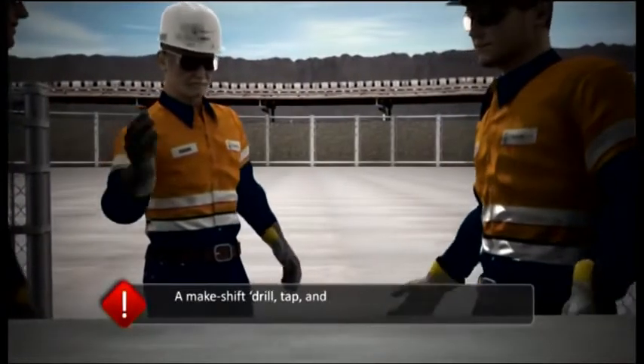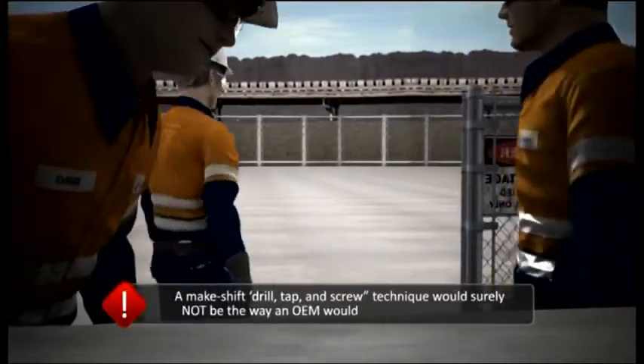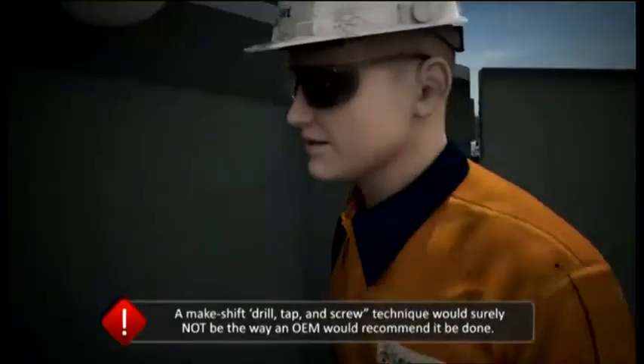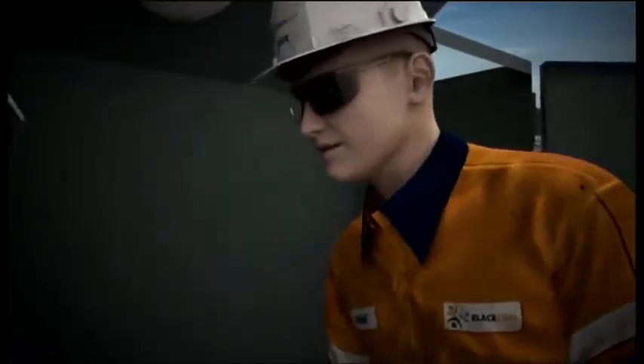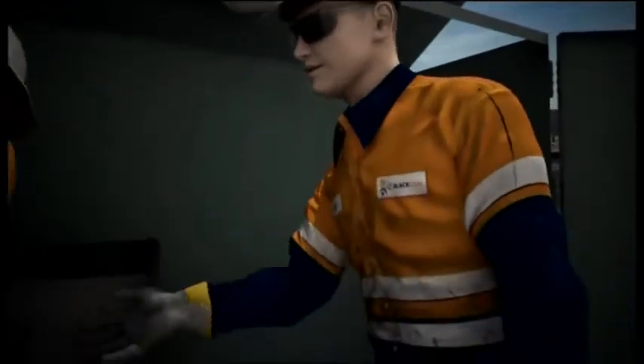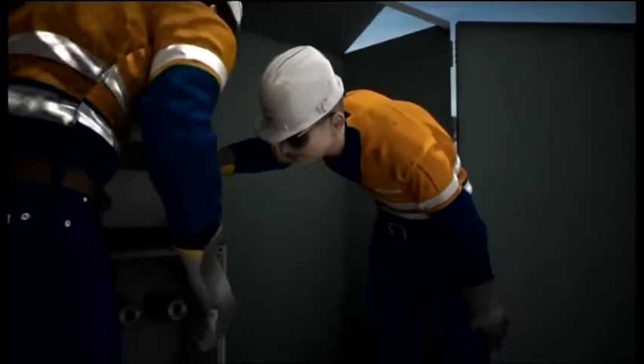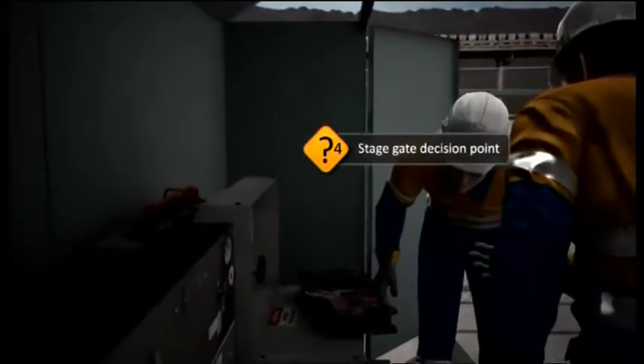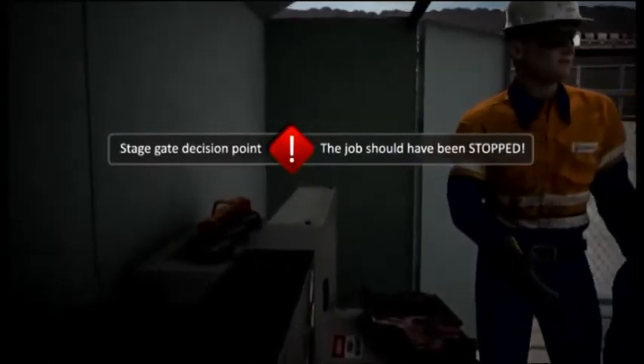Surely this would not be the way an OEM would recommend it to be done. To attempt to pry the mechanism over a mechanical interlock that was designed specifically to prevent its removal is the worst type of poor practice. This should never have been attempted, and again, the decision should have been to stop the job.